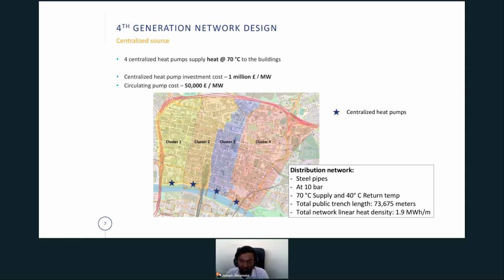If you look into the network parameters, we used steel pipes. We configured steel pipes in the software, and then we use 10 bar pressure with the supply and return temperature of 70-40 in this network. And then it turns out we require 73 kilometers of network in this particular area. And then we used the heat pump investment cost of 1 million pounds per megawatt.